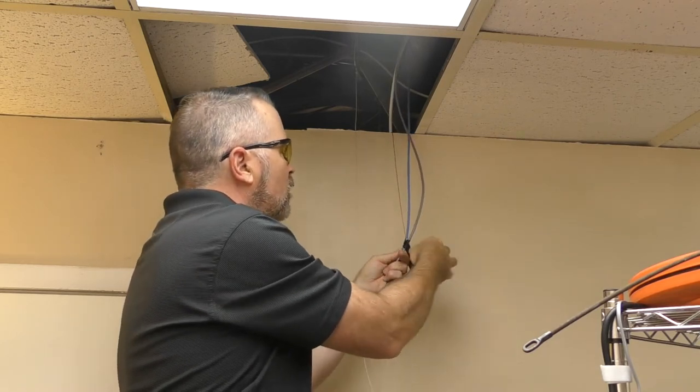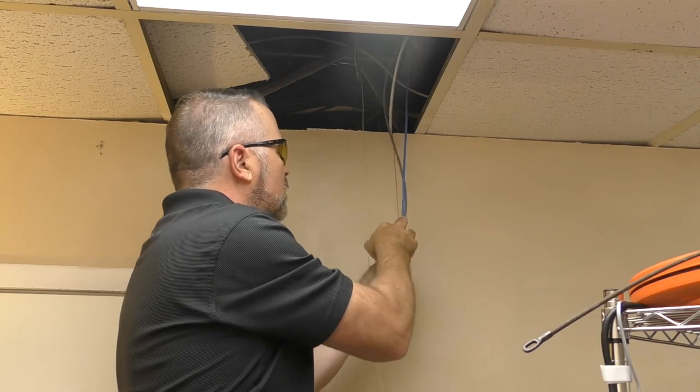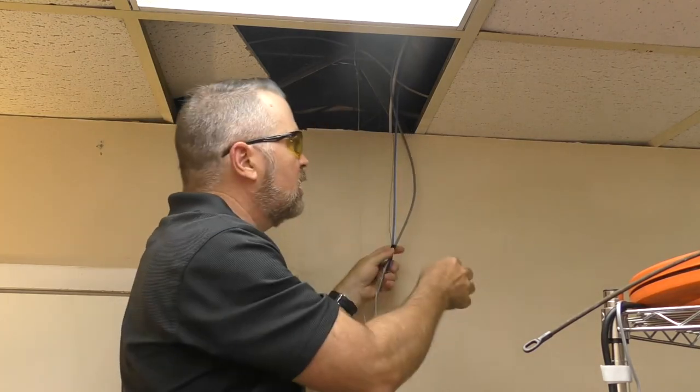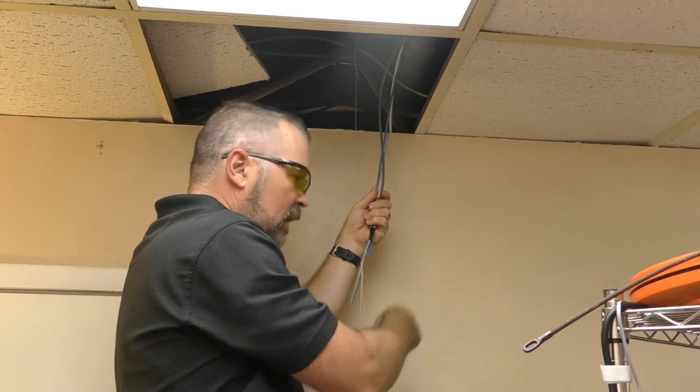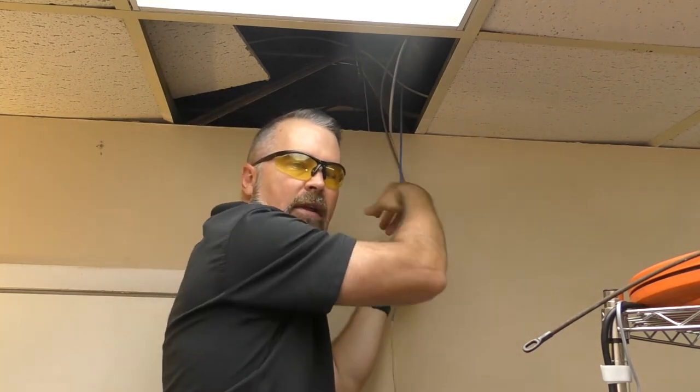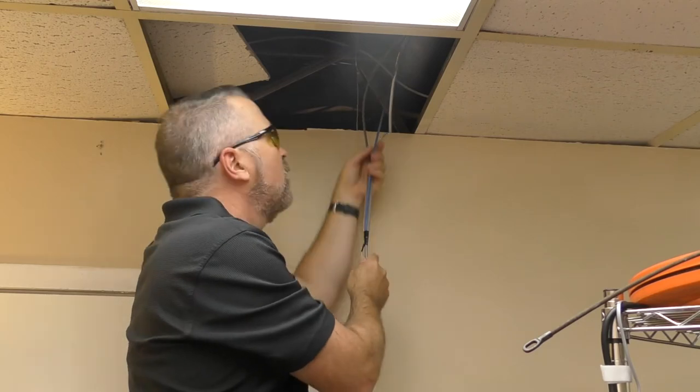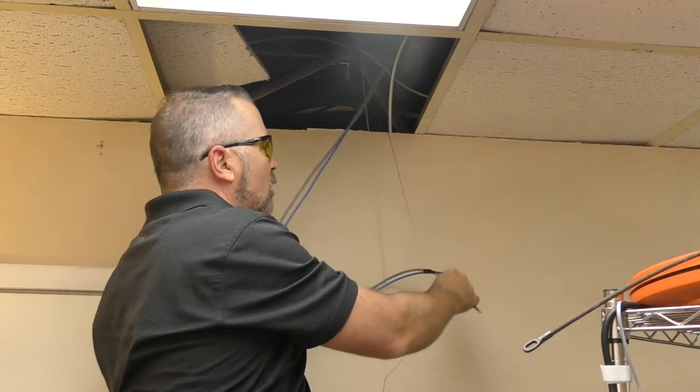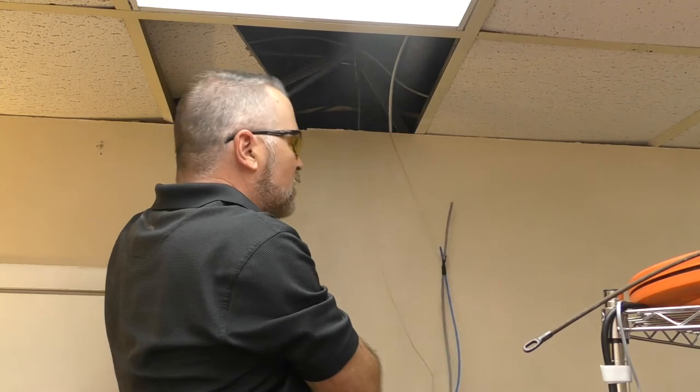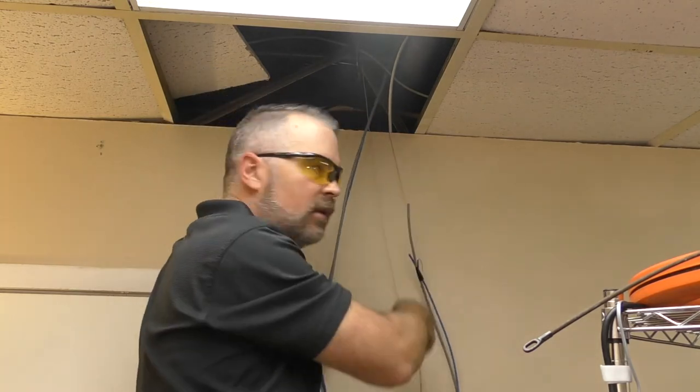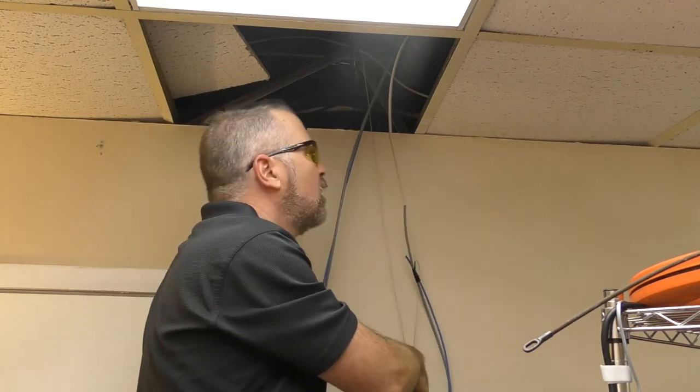And then just go down and pull your string. Now make sure though that when you do that, that you've got some slack on the cable in the ceiling. Because if you're trying to pull with the string, if you're trying to pull the whole entire cable from all the way at the far end, there's going to be too much resistance, the string will come off. So make sure you've got at least enough, probably about six foot of slack or eight foot of slack so that when you start pulling the string, there's no resistance as it pulls all the way down the bottom.